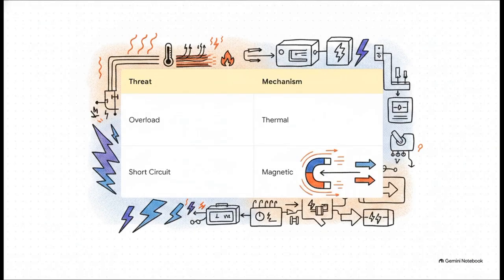Now, what's really interesting about this is how the breaker actually tackles these specific threats. For an overload, that slow traffic jam of current we talked about, the breaker uses a thermal mechanism. It literally heats up right alongside your wires, and when it gets just too hot, boom, it triggers the breaker to trip. But for a severe short circuit, where you absolutely don't have time to wait for things to slowly heat up, it relies on a magnetic mechanism. That massive sudden spike in current actually creates a really strong magnetic force that violently pulls the switch open and reacts almost instantly. The contacts separate, and that dangerously huge current is interrupted.